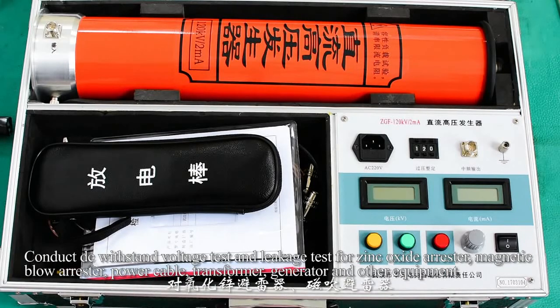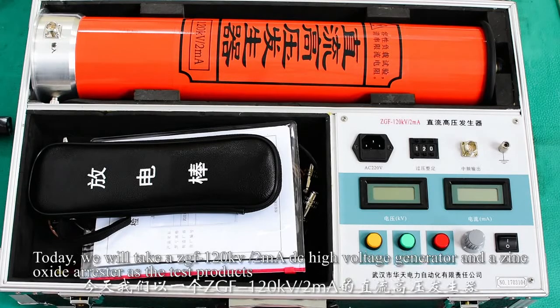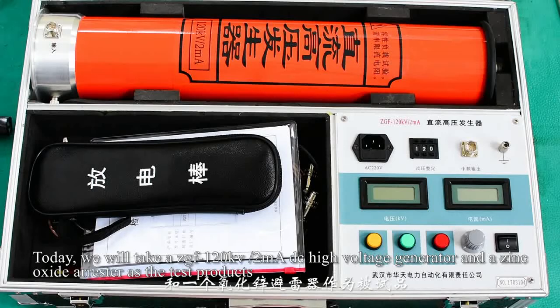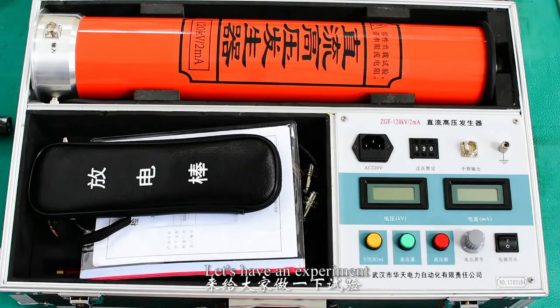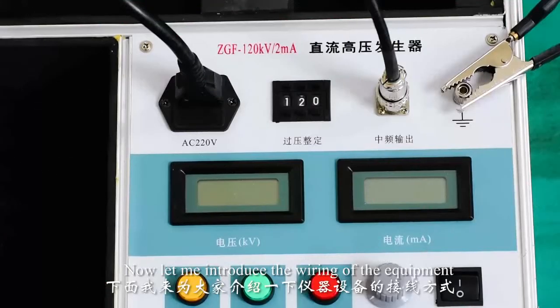It can conduct DC withstand voltage tests and leakage tests of zinc oxide arrestors, magnetic blow arrestors, power cables, transformers, generators, and other equipment. Today we will take a ZGF 120 kV 2 mA DC high voltage generator and a zinc oxide arrestor as the test products. Let's have an experiment. Now let me introduce the wiring of the equipment.